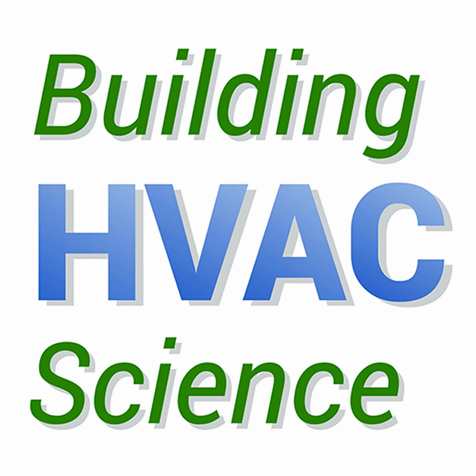Yeah, so we don't spray for that reason. We don't atomize. We basically have this manifold that distributes it right onto this media bed pad. And if you're familiar with a media bed, like in a cooling tower, you go to a major cooling tower, you're going to see like water just gushing down this thing and flying off and so on. So we come nowhere near that flow rate. We keep it, just as the manufacturer suggests, with quite a bit of safety factor, well below that.